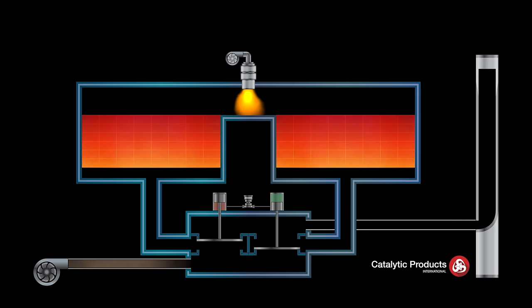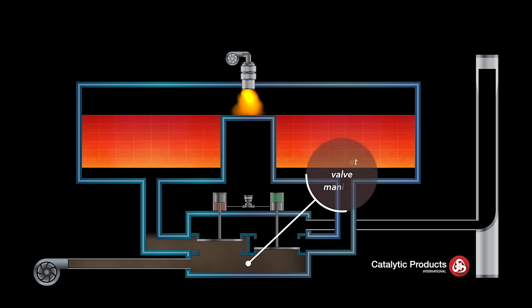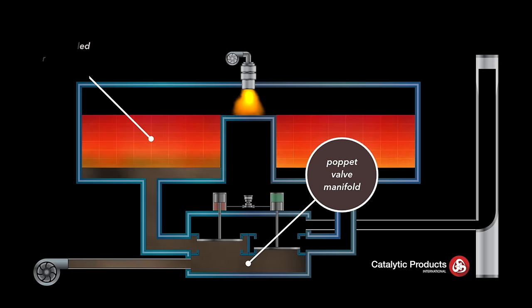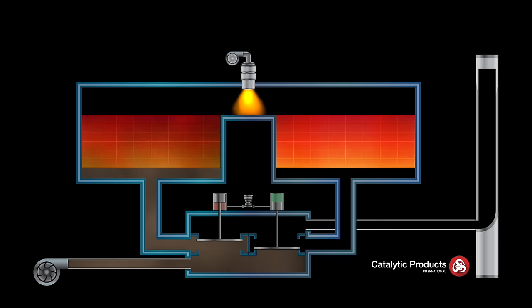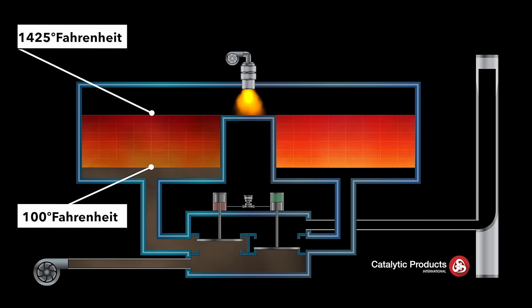The processed emissions are then directed into a poppet valve manifold where the untreated process stream enters the ceramic media filled regenerator column. The process stream is heated in the regenerator column from the inlet temperature of 100 degrees to over 1425 degrees Fahrenheit at the exit of the ceramic media.